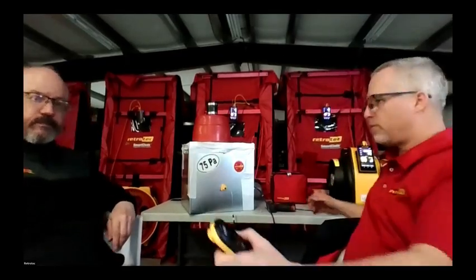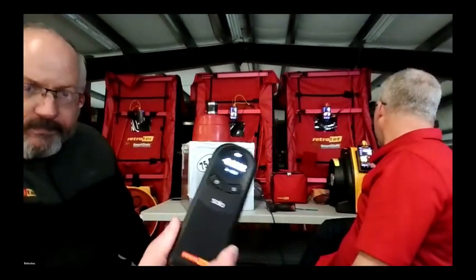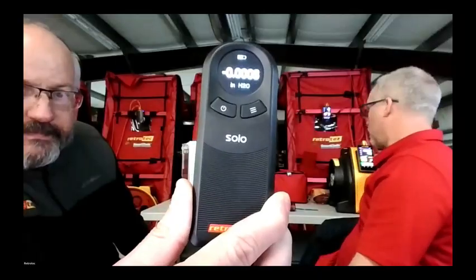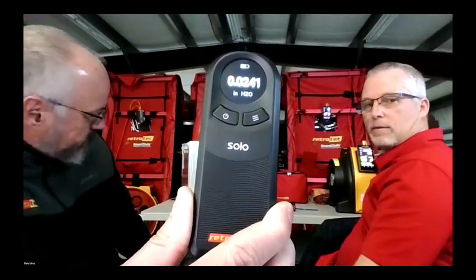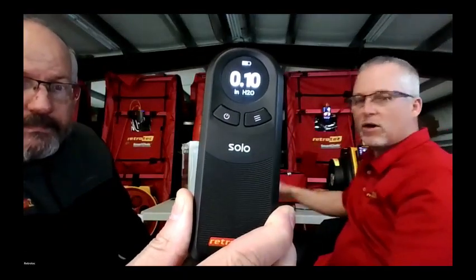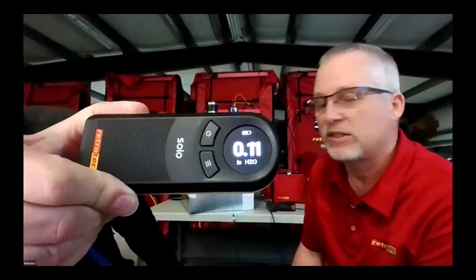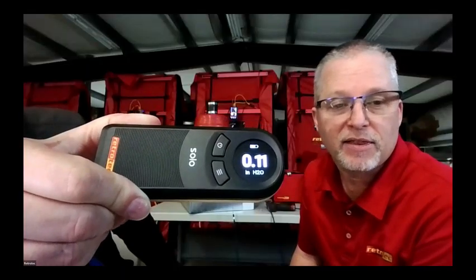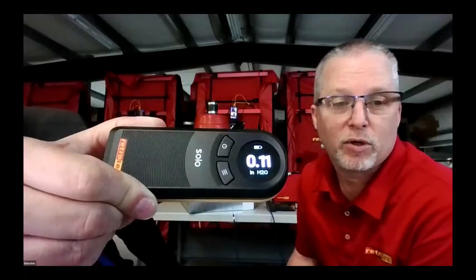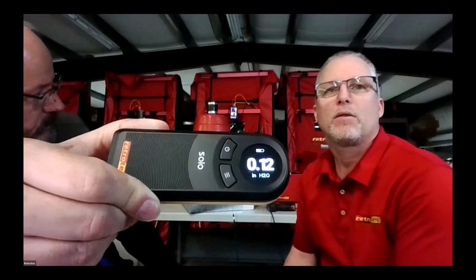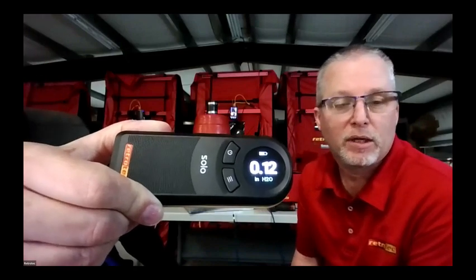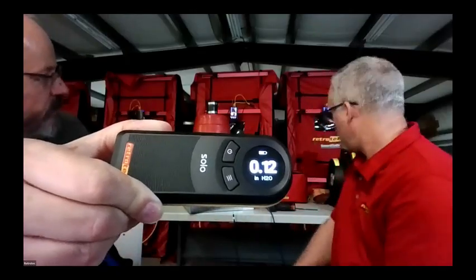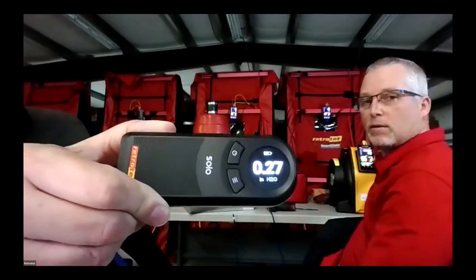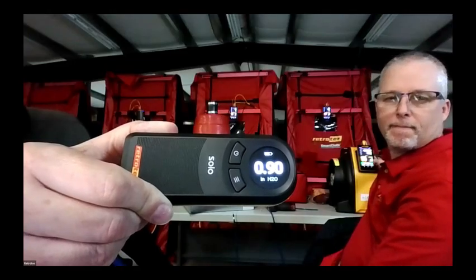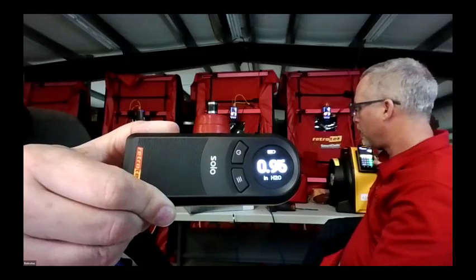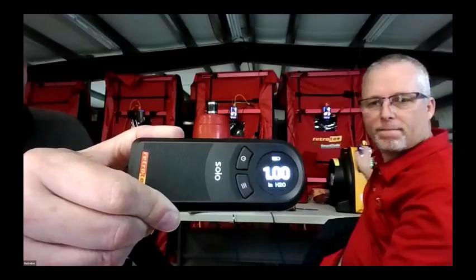We're going to demonstrate a little bit here by turning the power on. With the mini probe inserted into the unit like that, you can go by any insulation that's inside there and your airflow is going to be perpendicular to the end of the tube, so it's going to give you more consistent readings. It can also be used for laboratory work or clean rooms, just checking pressure differentials in there. It's great for spot checking too, just walking while you're doing a blower door test and using the unit to check underneath doorways and under sills.